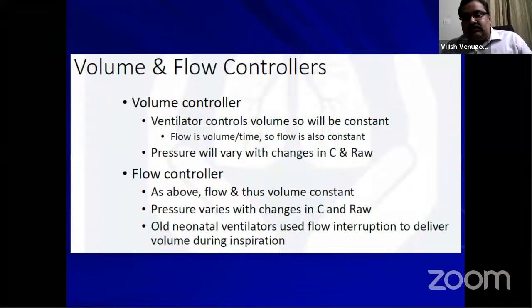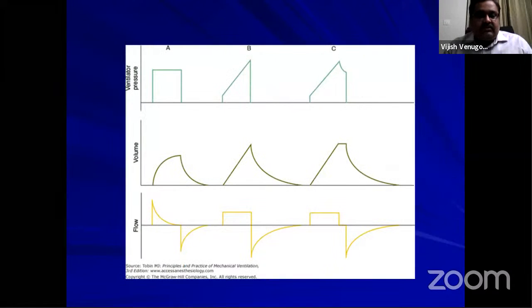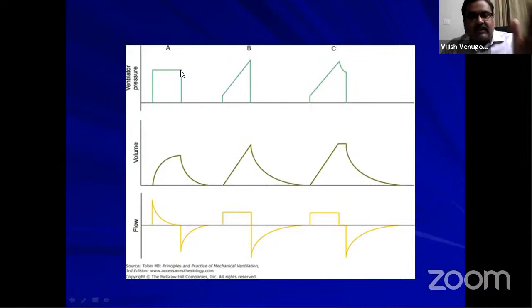Coming to volume and flow controllers, the volume ventilator will control the volume. So the volume will be constant. But what is flow? Flow is volume by time. So here, since volume is constant, the flow also will be constant. But what happens here is the pressure will vary with the changes in the compliance as well as the resistance offered by the airway. Now coming to the third one, that is the flow controller. Like a volume controller, the flow and volume will be constant and pressure will be varying. If you look at this picture or the graphics, in A, you can see that on the pressure part, there is a plateau. So that means that is a pressure controller. In the second, B, you can see that in the flow, there is a plateau.